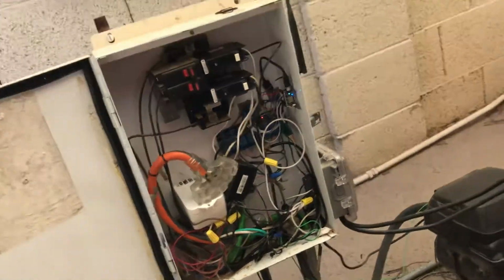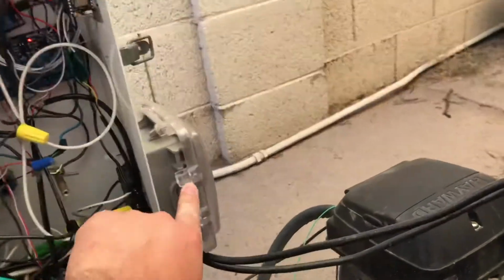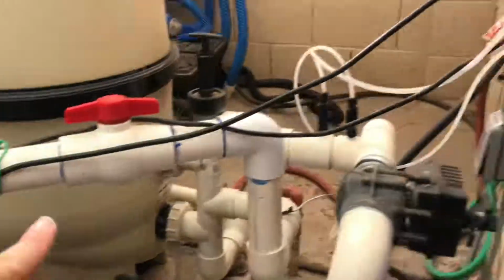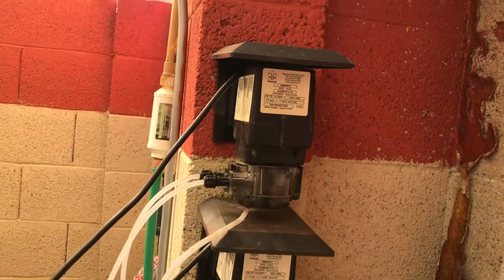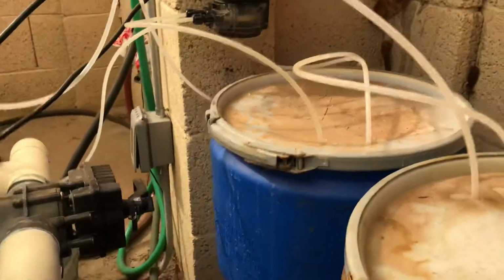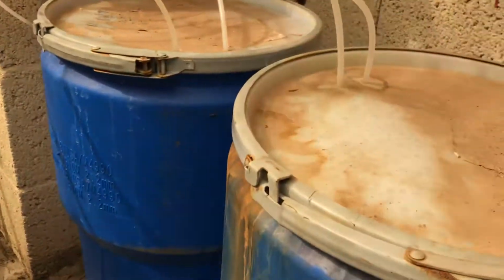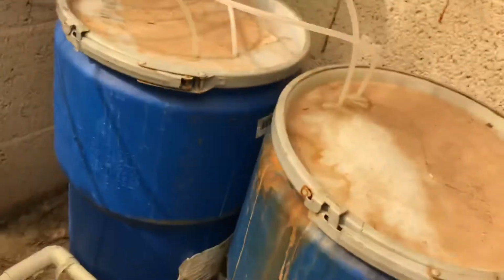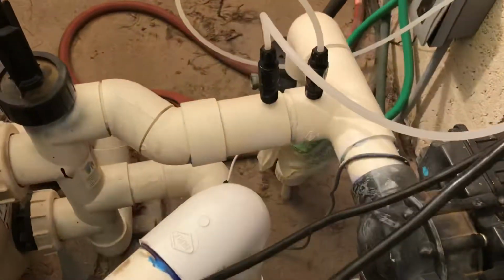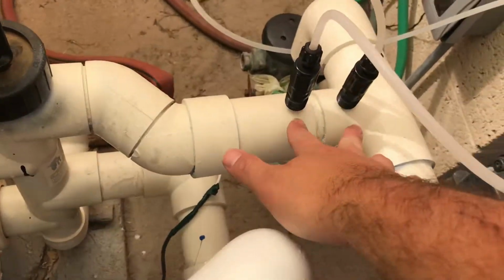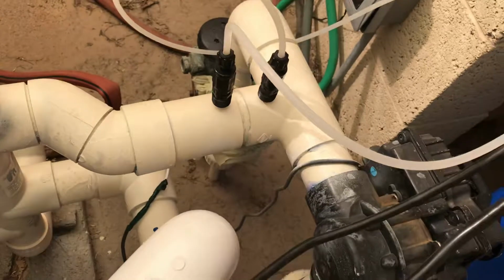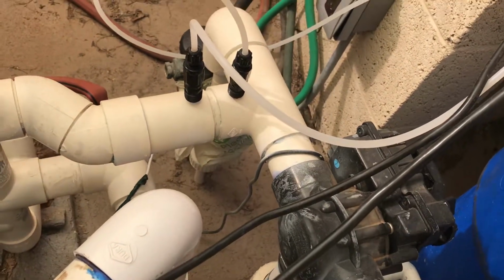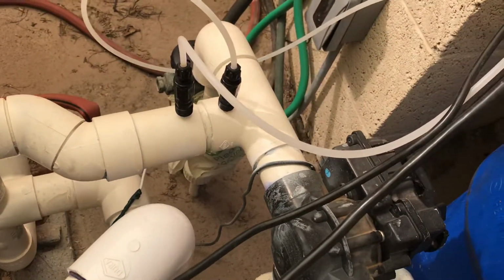2 of the other relays control this outlet, top and bottom, right here. Plugged into the outlet are a couple Stenner pumps that pump chemicals - this is the chlorine tank, this is the muriatic acid tank. Those get injected directly into the lines after the filter and after the pump, so there's no wear and tear on the equipment; the chemicals get pumped right into the return lines of the pool.